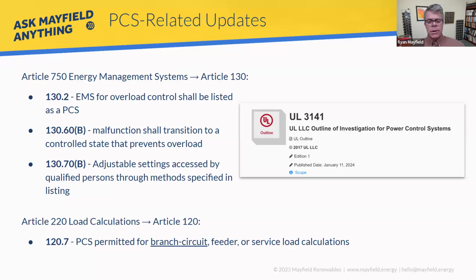So let's talk about this a little bit more, the overload function. It's a pretty big change. We had it already mentioned in 705.13. This is allowing us to have potentially more sources, more PV, more batteries, more power sources connected to a bus bar than we would have in the past. It's because our PCS - correct me anywhere I get this wrong - is monitoring and making sure that the output of our energy, whatever those sources of power are, whether it's solar, batteries, utility, we're not going to overload that bus bar. So we have this way of controlling that and not having to use brute force in terms of saying you can only put 32 amps on this residential bus bar. Now code is saying, sure, you can put 60 amps on, but we got to make sure that bus bar is not overloaded.